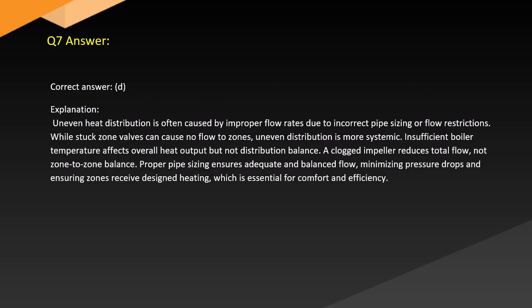Answer. Correct answer, D. Explanation. Uneven heat distribution is often caused by improper flow rates due to incorrect pipe sizing or flow restrictions. While stuck zone valves can cause no flow to zones, uneven distribution is more systemic. Insufficient boiler temperature affects overall heat output but not distribution balance. A clogged impeller reduces total flow, not zone-to-zone balance. Proper pipe sizing ensures adequate flow and balance, minimizing pressure drops and ensuring zones receive designed heating, which is essential for comfort and efficiency.